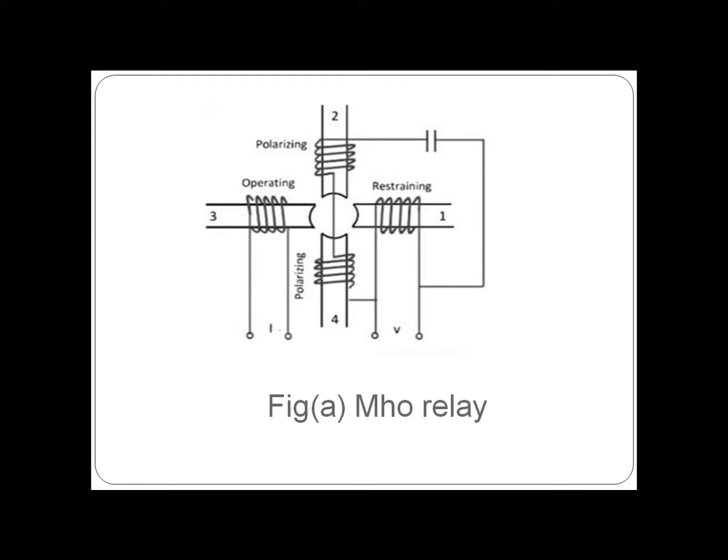The interaction of fluxes due to poles 2, 3, and 4 produces operating torque, and due to poles 1, 2, and 4, controlling or restraining torque is obtained. The 1-2-4 pole produces restraining torque; the 2-3-4 produces operating torque. A series capacitor is connected to provide memory function.